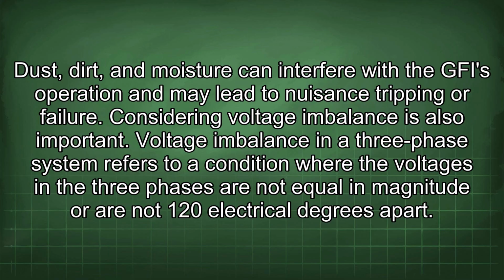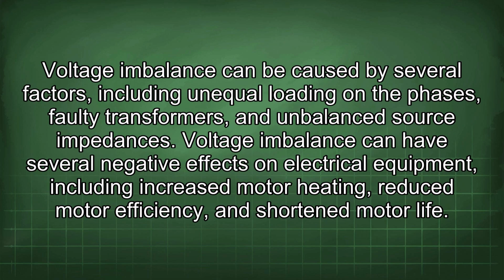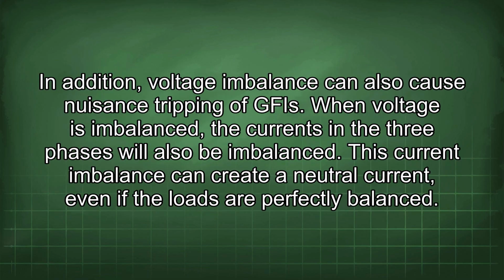Considering voltage imbalance is also important. Voltage imbalance in a three-phase system refers to a condition where the voltages in the three phases are not equal in magnitude or are not 120 electrical degrees apart. Voltage imbalance can be caused by several factors, including unequal loading on the phases, faulty transformers, and imbalanced source impedances. Voltage imbalance can have several negative effects on electrical equipment, including increased motor heating, reduced motor efficiency, and shortened motor life. In addition, voltage imbalance can also cause nuisance tripping of GFI.